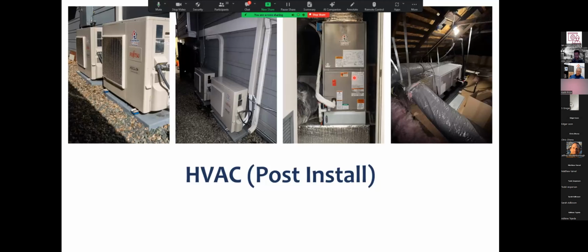So most of the time when this unit is cycling, it's never going over 10,000 BTUs, and it's mostly between 10,000 and 5,400. And with this type of equipment, it's really hard to tell exactly what BTUs it's putting out. So a bit of that is assumption based on energy use. But when these things are running 5,400 BTUs on low, that unit is using somewhere in the neighborhood of 400, 500 watts. And the maximum capacity at 24,000, it's using like 2,100 watts or 2,000 watts. So not a lot of energy at all.